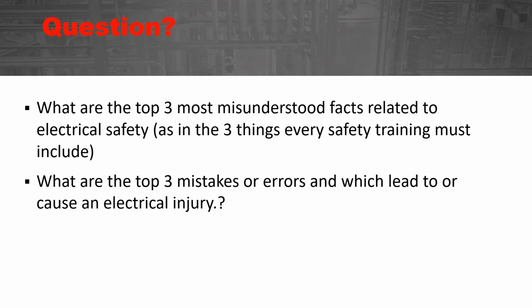I hear quite often when I'm teaching, oh, our people, we don't do any live work. Well, okay, that's fine, but until the equipment is put into an electrically safe work condition, you have to consider it energized. That means until you have established and verified, there are 8 steps in establishing and verifying the equipment is in an electrically safe work condition. Until you have done that, the equipment is energized. You have to treat it as energized, and I think that is absolutely the biggest.